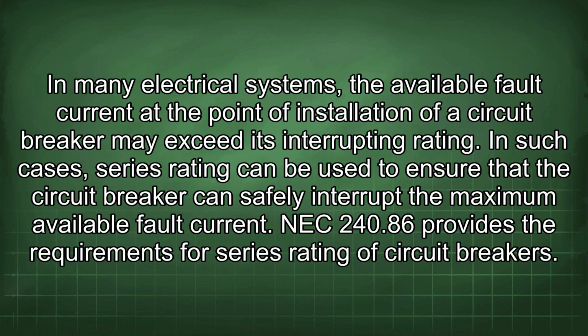In many electrical systems, the available fault current at the point of installation of a circuit breaker may exceed its interrupting rating. In such cases, series rating can be used to ensure that the circuit breaker can safely interrupt the maximum available fault current. NEC 240.86 provides the requirements for series rating of circuit breakers.